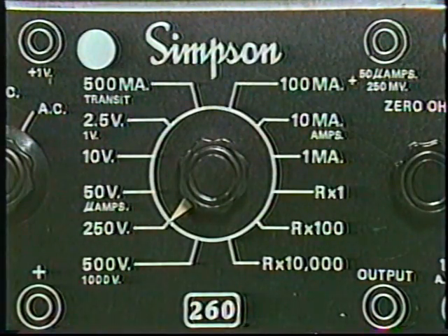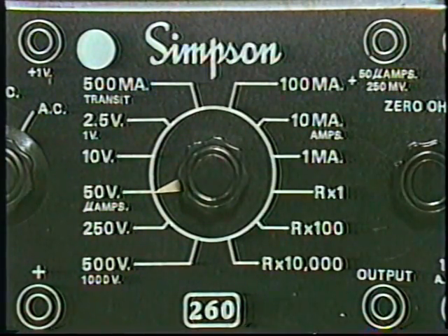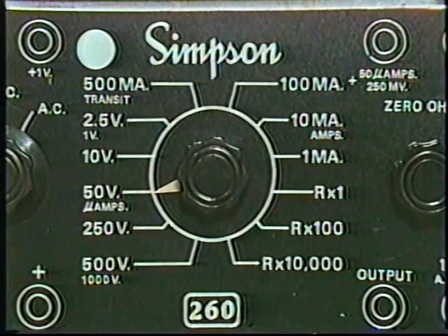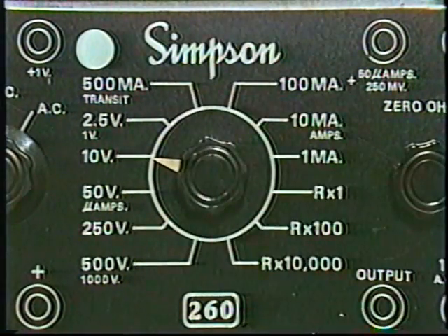To confirm this, set the volt-ohm meter to the next voltage scale that is higher than the battery's voltage. For example, if you're working on a 36-volt battery, use the 50-volt scale. Now we're going to check the voltage from the negative terminal to the frame, because we already identified that the leakage is on the positive side. It may be necessary to use a lower voltage scale in order to get a more accurate reading.